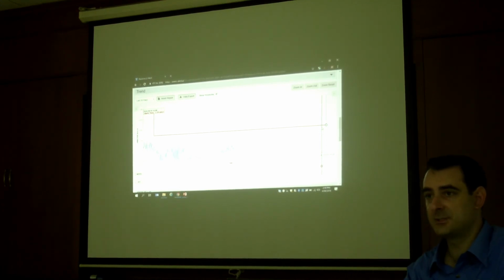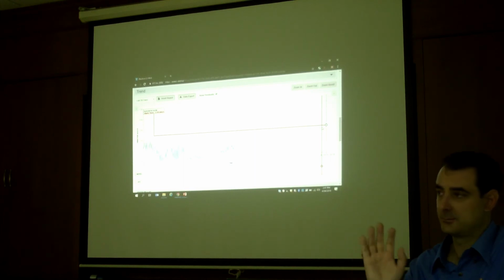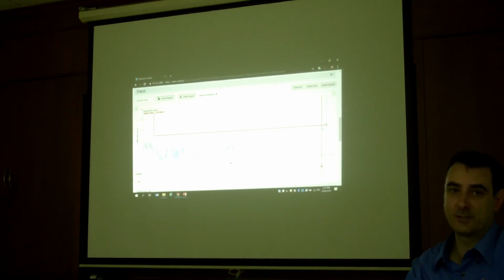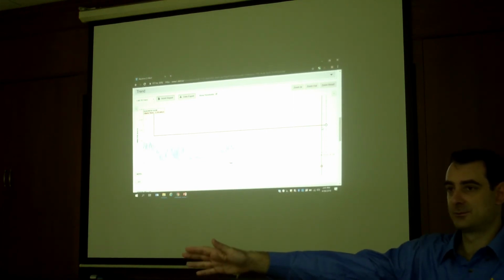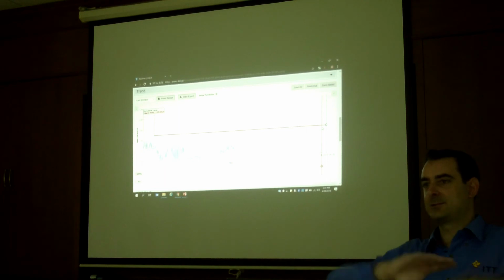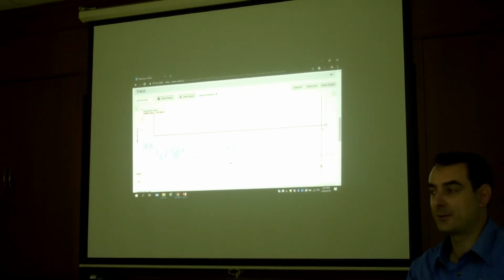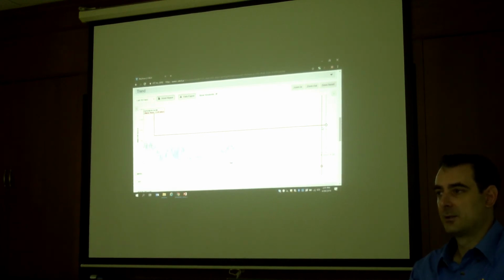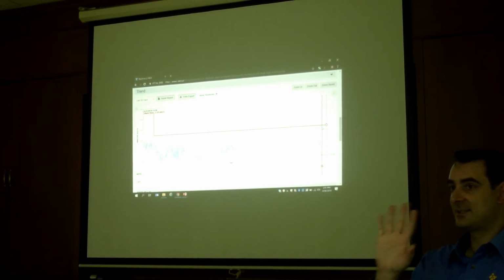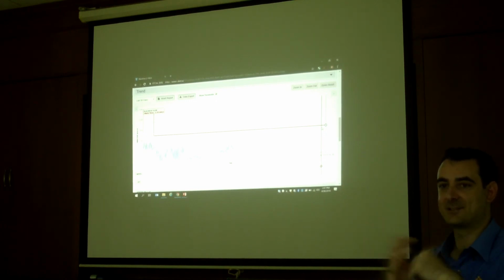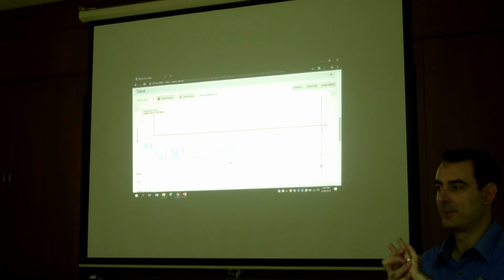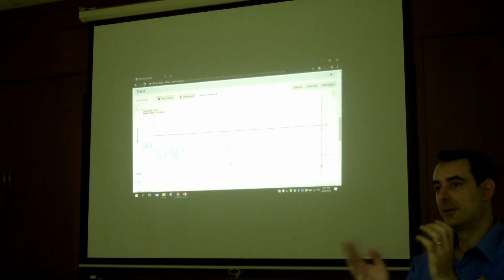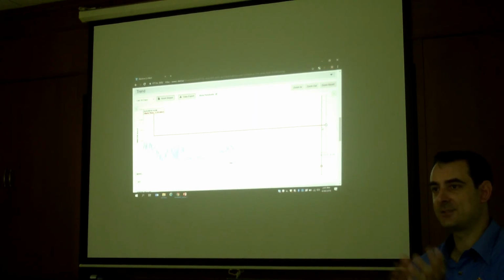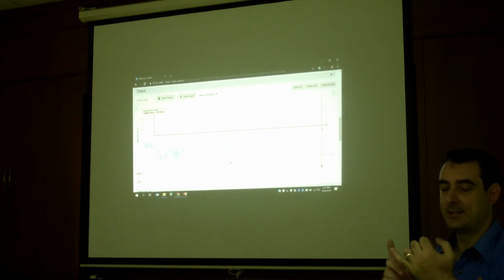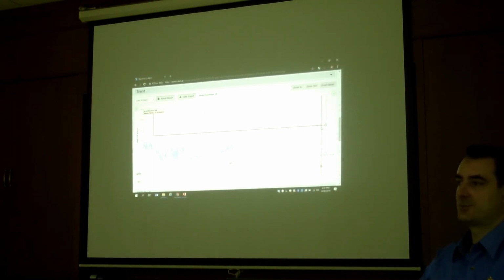Sometimes we get intermittent transmissions when there's a lot of interference. If there's too much, it'll block. Now, a tank terminal, for example, where I'm working with a couple of customers' iAlerts, it will not go through the tank. But it'll do all the straight lines either side between the tanks, quite a good distance. And it's different to Wi-Fi. Wi-Fi will not send signal through a steel mesh fence. It's like a Faraday cage, it doesn't do it. But the Bluetooth will. It will go through it. So the technologies are different. There's positives and negatives on each. We chose to use Bluetooth because of the low energy, and it just happens that it's got different advantages.